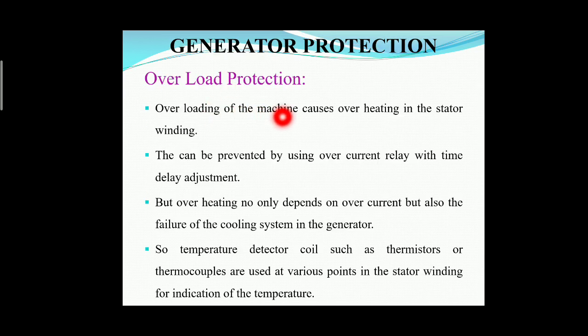Overloading of the machine causes overheating. Due to overloading, overheating occurs in the stator winding. That can be prevented by using overcurrent relays with time delay adjustments.